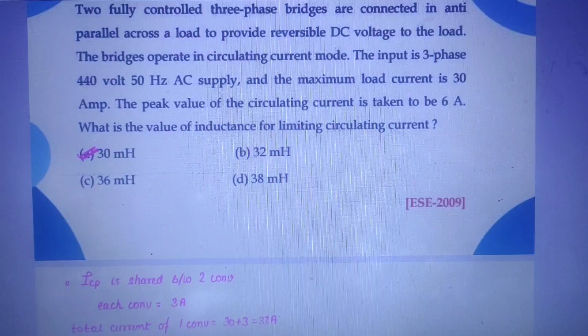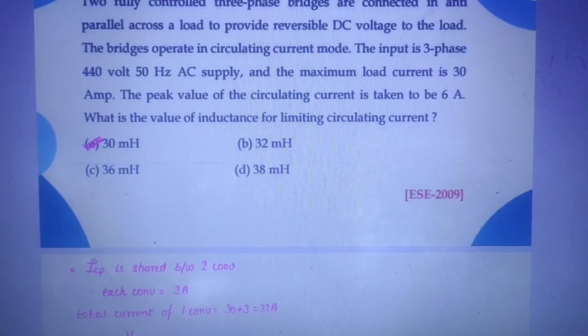Two fully controlled 3-phase bridges are connected in anti-parallel across a load to provide reversible DC voltage to the load. The bridges operate in circulating current mode. The input is a 3-phase 440 volts 50 Hz AC supply. Maximum load current is 30 amperes. Peak value of circulating current is 6 amperes. He is asking to find the value of inductance to limit the circulating current.